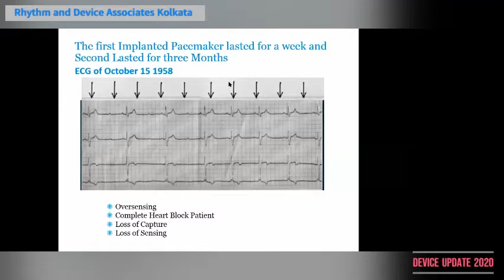Over sensing? No, then the pacing pulse will not happen. Loss of capture? I think the pacing spike is going in its own way and the ECG is going in its own way. There is no synchrony between the pacing spike and the complex. Exactly, sir, you're right. So clearly, as people have started answering it as loss of capture, this was happening within a week, and we have developed a new device which was able to pace the heart.